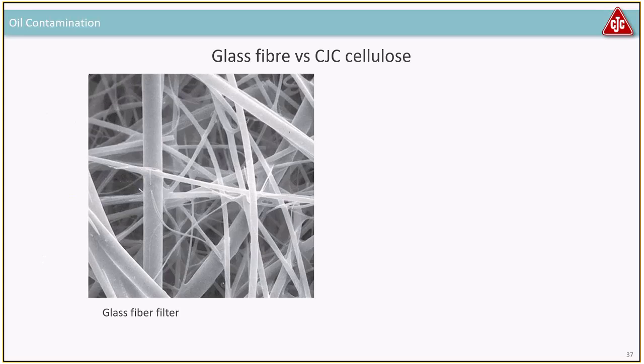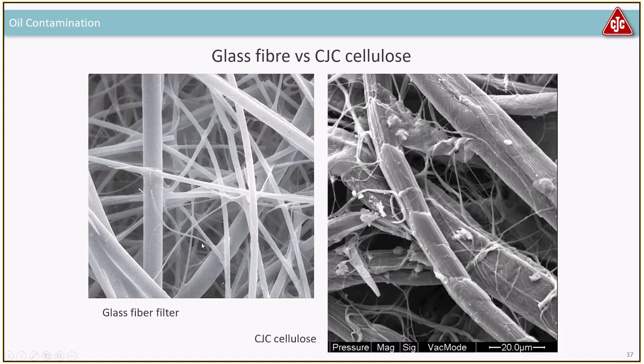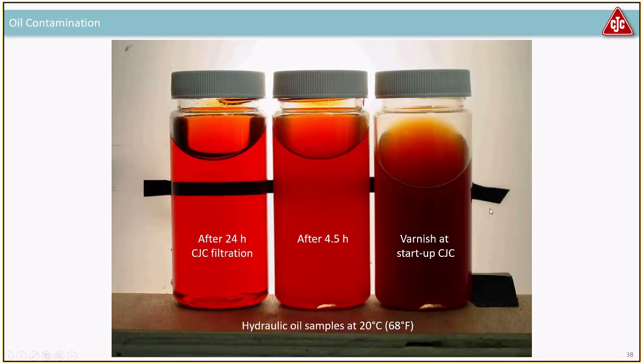If you zoom in on glass fibers versus CJC cellulose fibers, the glass fibers are quite uniform in size and particles are blocked by the hole sizes. In the CJC cellulose, there are big structural fibers of about 20 microns that hold the structure in place, plus many tiny nano fibers — a patent from CC Jensen — enabling much finer filtration to remove varnish, particles, and water. Here's a demonstration: a startup hydraulic system where after 4.5 hours you can start to see through the bottle, and after 24 hours the particles and varnish have been removed — all because of the depth material.